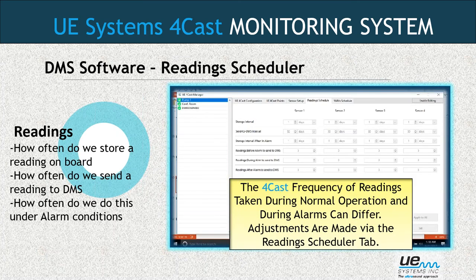Here's our reading scheduler tab. I mentioned this earlier. How often do we store a reading on board the 4Cast? How often do we send a stored reading over to our DMS software, for a permanent historical record? And how often do we do this once we've hit an alarm condition? Most of the time, we're going to do it more frequently once we've hit an alarm condition. So we're taking readings during normal operation, and then we're taking readings before, during, and after the alarm took place.